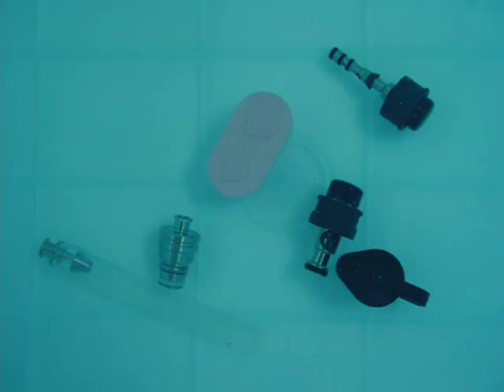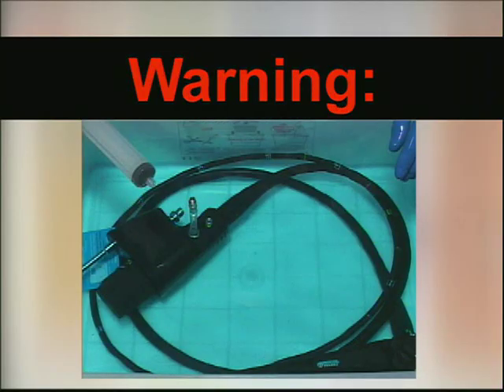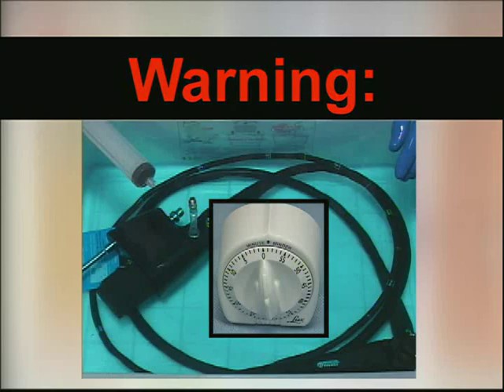The removal of component parts and cleaning adapters from the endoscope will eliminate the risk of mated surfaces not being exposed to the liquid chemical germicide. Warning: it is imperative that all internal surfaces of the channels are in contact with the disinfecting solution for the time period recommended by the manufacturer of the solution.